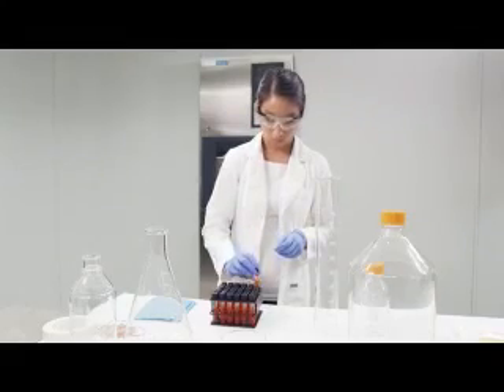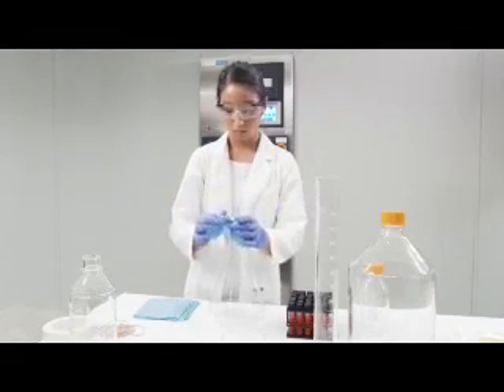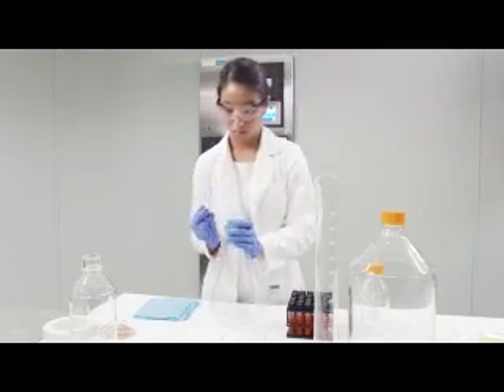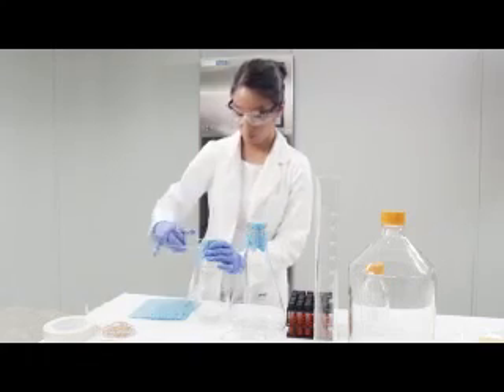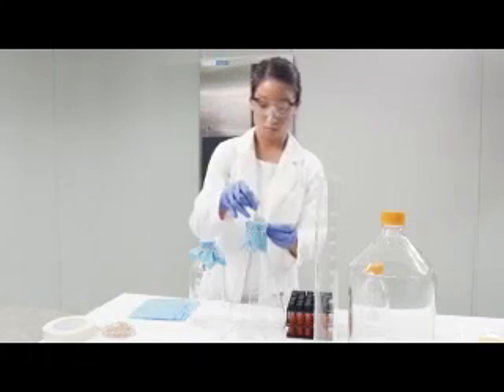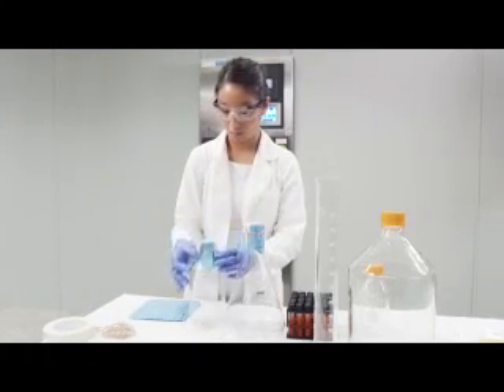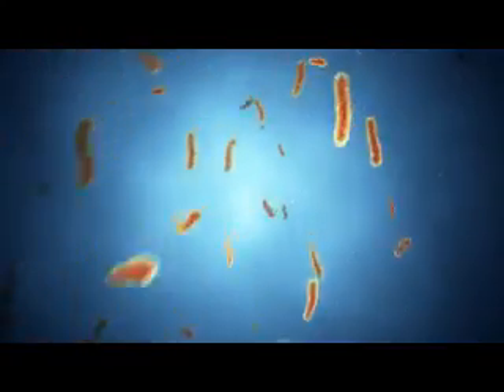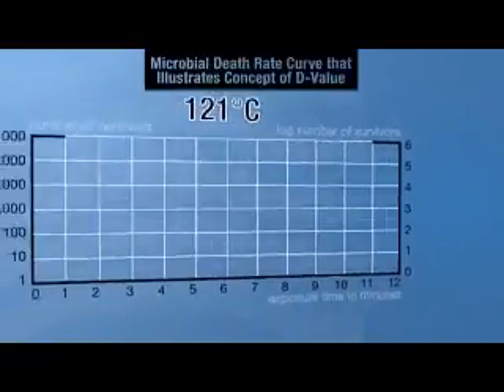In order to effectively sterilize glassware, liquid media, biohazard bags, or other items, it is important to understand a few basic principles of steam sterilization. Saturated steam contains a very high amount of energy that is lethal to even the most resistant of bacteria spores. However, in order to kill these spores or any microorganism, the steam must make contact with the organism. Since not all organisms die at the same rate, there is also a time factor involved in sterilization.